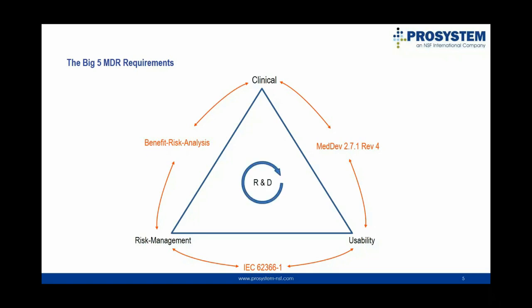If you start R&D work for a new medical device, the new regulation requires that you make no false claims about your product, and based on your claims, you have to define an input statement for your design work and particularly use that intended use or intended purpose statement as an input for your risk management and usability activities. The expectation from the MDR for how an intended purpose statement is phrased is much more detailed than the requirement in the existing Medical Device Directive. As a side remark, in the landscape of in vitro diagnostic medical devices, the level of detail for defining an intended purpose statement is even very, very precise, based on an existing checklist.